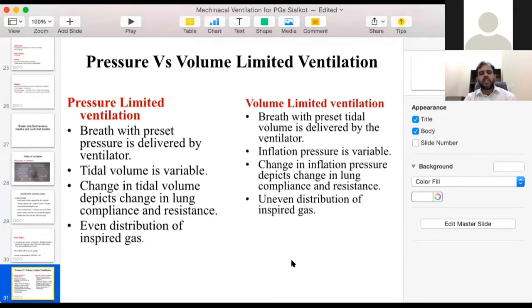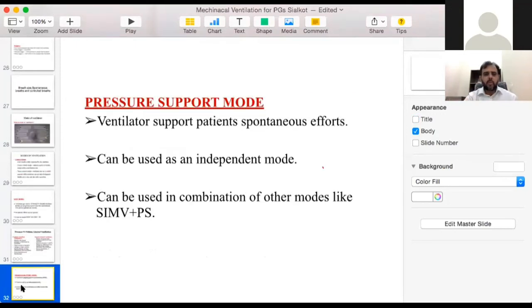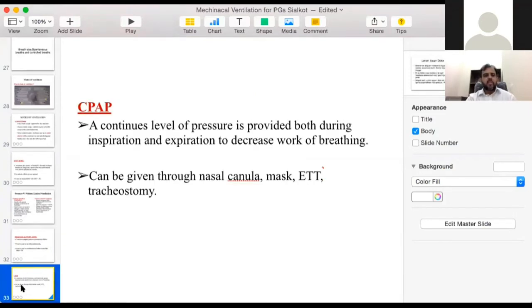There is a pressure controlled ventilation and volume controlled ventilation. We have already discussed that the settings where we are adjusting PIP and pressure, that is pressure control mode, and the other one where we are using volume, that is the volume controlled ventilation. So these are the two comparable modes. Pressure support mode, this is just a weaning mode. Simply the patient is spontaneously breathing, we just add a pressure support for each breath. There will be support, and the breaths will be of good size and give good tidal volume and improvement in the oxygenation. CPAP we have already discussed.